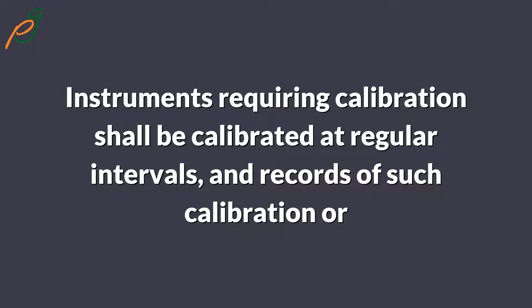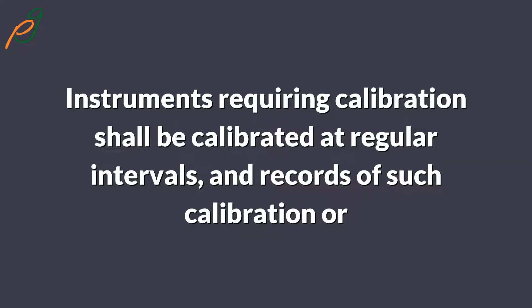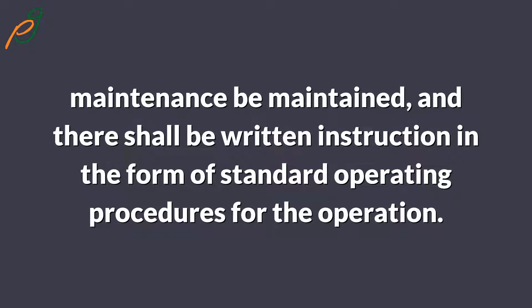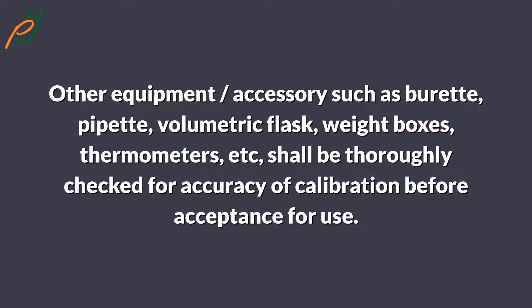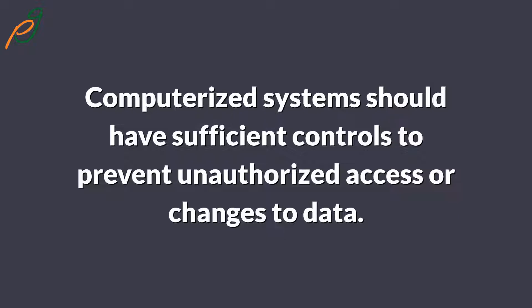Instruments requiring calibration shall be calibrated at regular intervals and records of such calibration or maintenance shall be maintained. There shall be written instructions in the form of standard operating procedures for the operation of equipment. Other accessories such as burettes, pipettes, volumetric flasks, weight boxes, thermometers, etc., shall be thoroughly checked for accuracy of calibration before acceptance for use. Computerized systems should have sufficient controls to prevent unauthorized access or changes to data.